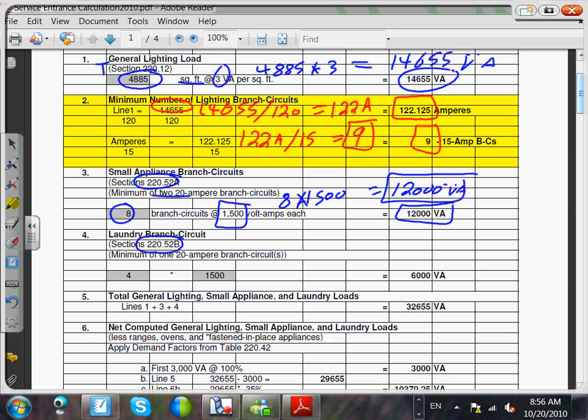And based on laundry circuit for every dwelling unit, and based on, what did we say based this one on? Based on 1500 volt amp. Now, how many laundry circuits do we, first of all, do we have laundry circuits? Have we provided laundry circuits in the apartments? There's no laundry circuit in the apartments. How many laundry circuits did we provide in the utility room? Did we have 4 or 2? We provided 2, in our example. So across this number, I'm going to have 2.